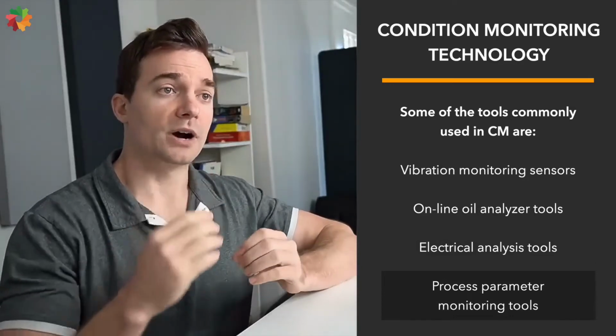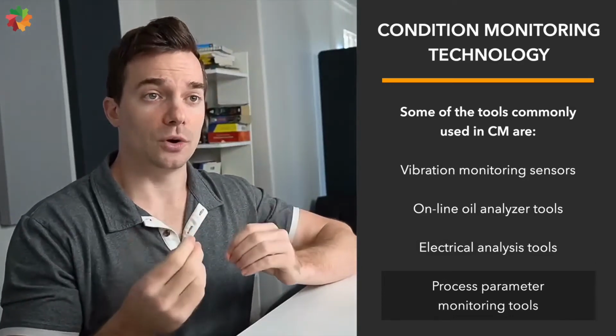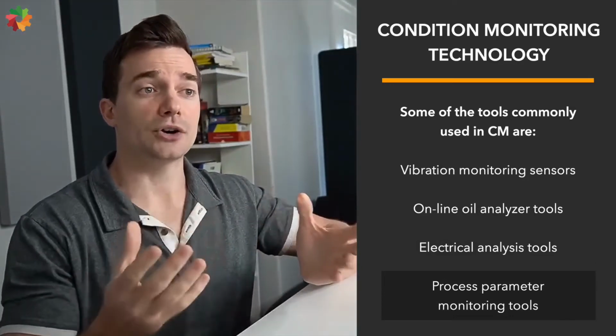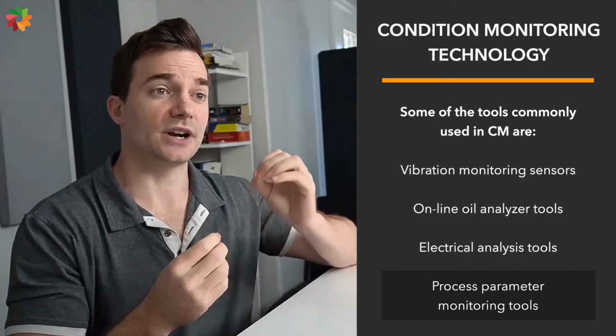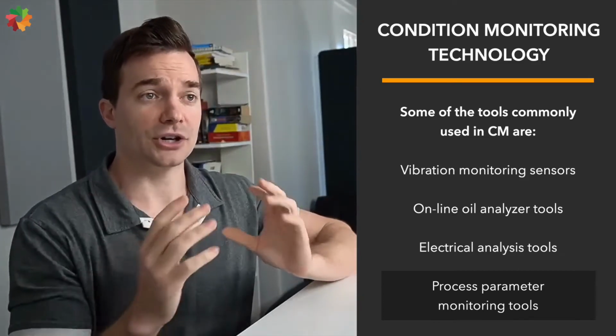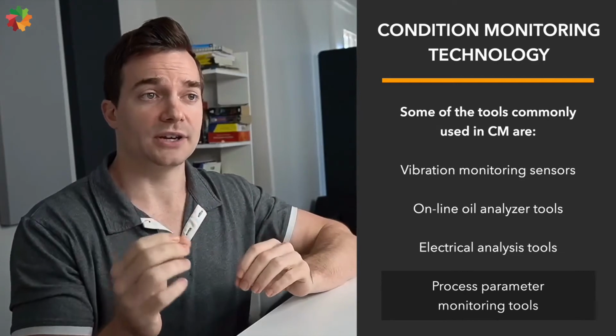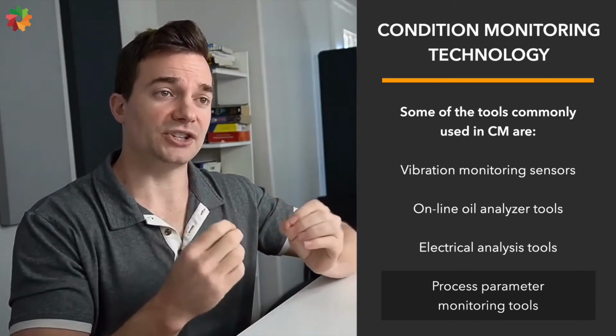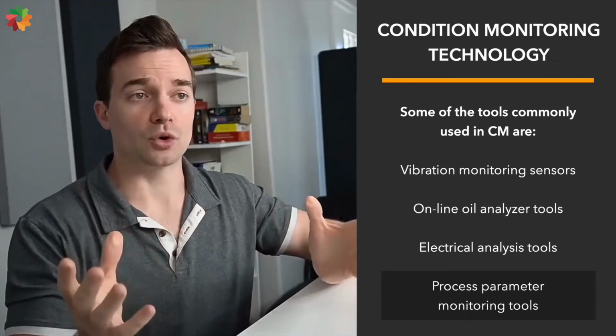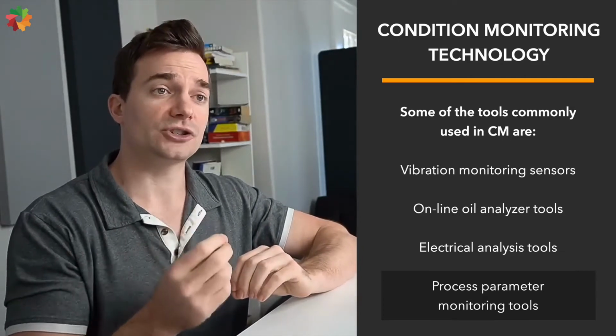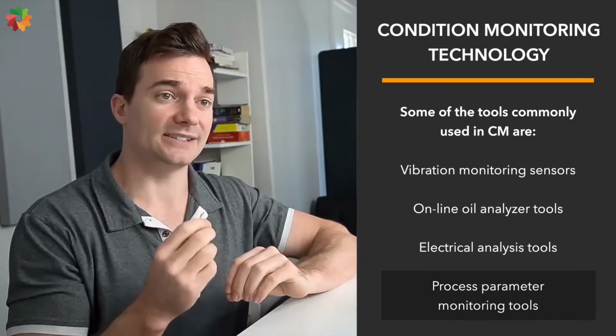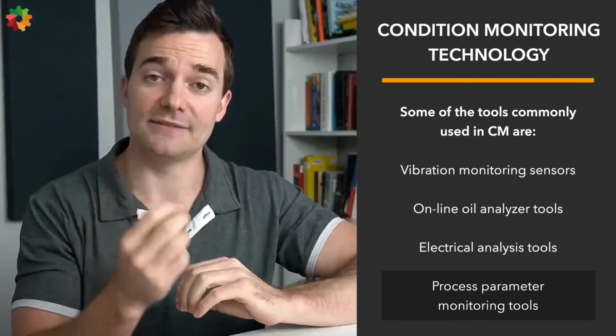And we have four, process parameter monitoring tool. This may include measuring and monitoring process parameters such as differential pressure, line pressure, temperature, and flow velocity to detect gradual degradation and respond before they spiral out of control. The data obtained through the sensors is usually compared with the baseline data to detect anomalies and deviations.